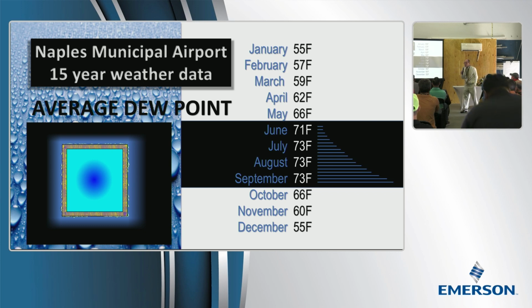One of the things that's extremely predictable is that the climate zone 1 dew point, at least at the Naples Municipal Airport over the last 15 years, has been an average of 73 degrees. Now, the reason that's important is because that tells you where the duct has to be, or the air handler cabinet. In other words, in our climate in Naples, Florida, if you're going to have an air handler cabinet that's cooler than 73 degrees, expect it to get wet. And that would not be a malfunction. That would just be normal.